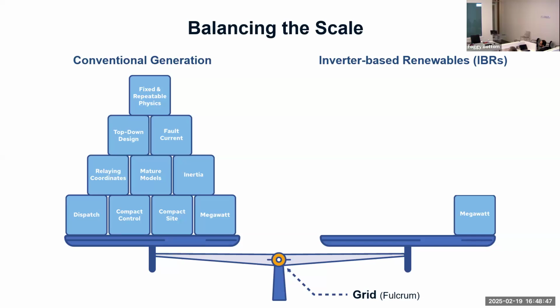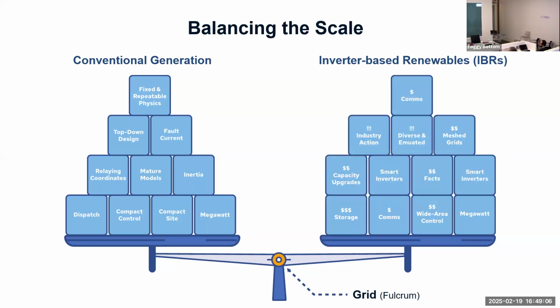The site's controlled, it has inertia, the model is mature—I know how it's going to show up in simulation, and I can do all sorts of analysis. It's going to give me fault current; when there's a problem, it rushes fault current in. If I want that with inverter-based generation, I need to strap on a lot of technology, and there are costs with that—not only costs, but complexity. We're going to figure this stuff out, but it's challenging.